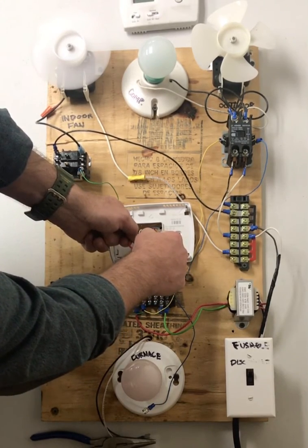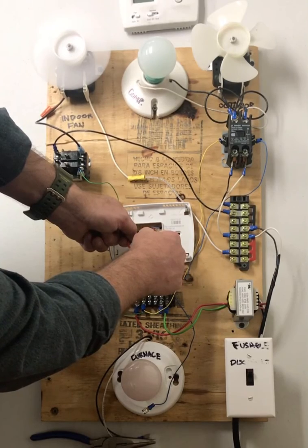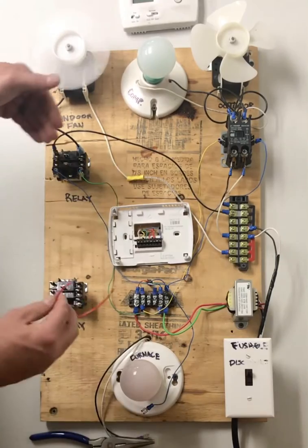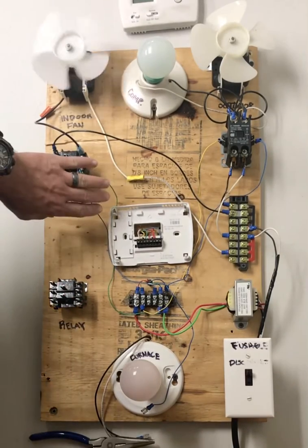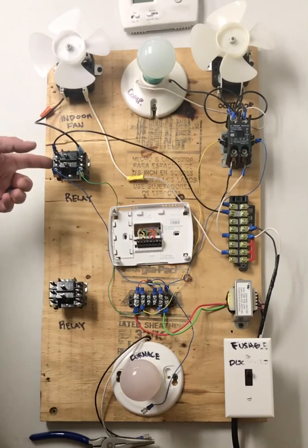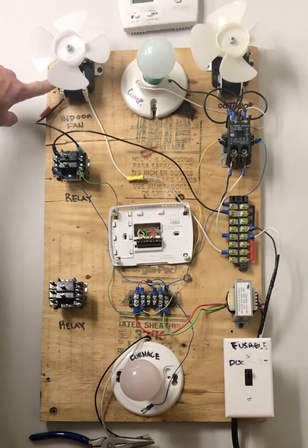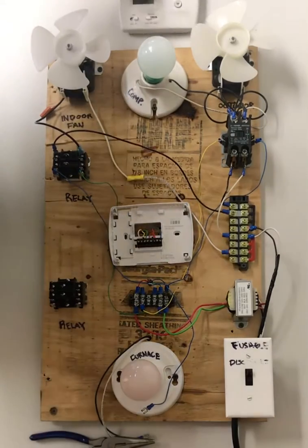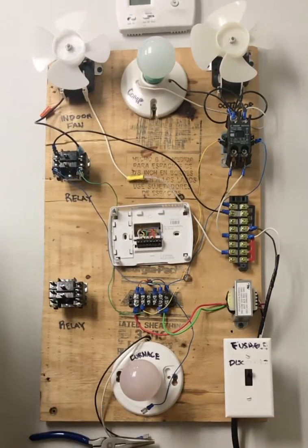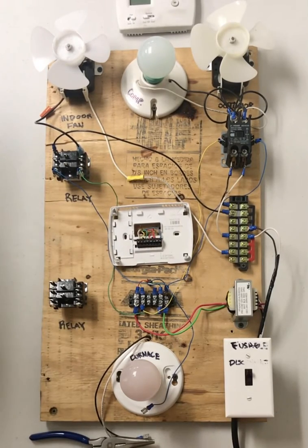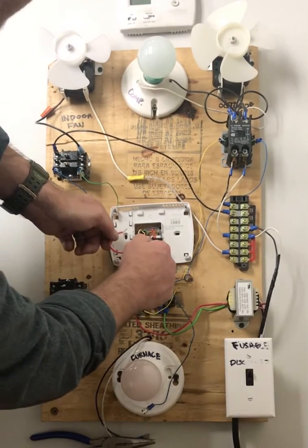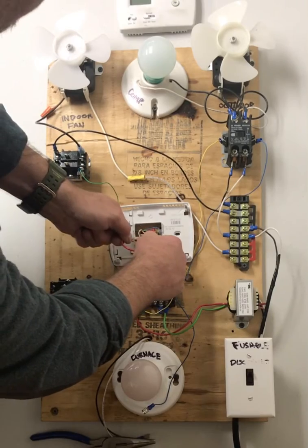If your fan turns on, you know your thermostat's good because your wiring's obviously good. Every part in the system is good. You don't have a broken wire, you don't have a bad relay, you don't have a bad fan motor. What you have is a bad thermostat. But she said she wasn't getting anything with a cooling call. So which terminal is used when we make a cooling call? It's your Y terminal.